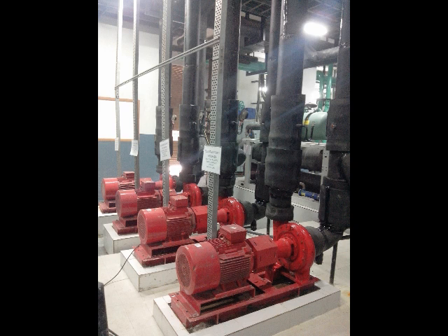These are 4 secondary pumps. 1 or 2 or 3 pumps can be run at a time as per load demand. The outlet of the chiller is fed to all the AHUs, TFAs, CSUs, FCUs, high wall units and cassette units through these pumps. These pumps also have inlet and outlet pressure gauges to monitor the pressure in the line. These pumps are VFD control pumps, that is, variable frequency drive control. If the load is less, the VFD will get a signal through pressure switches and control the speed of these pumps and save huge energy.